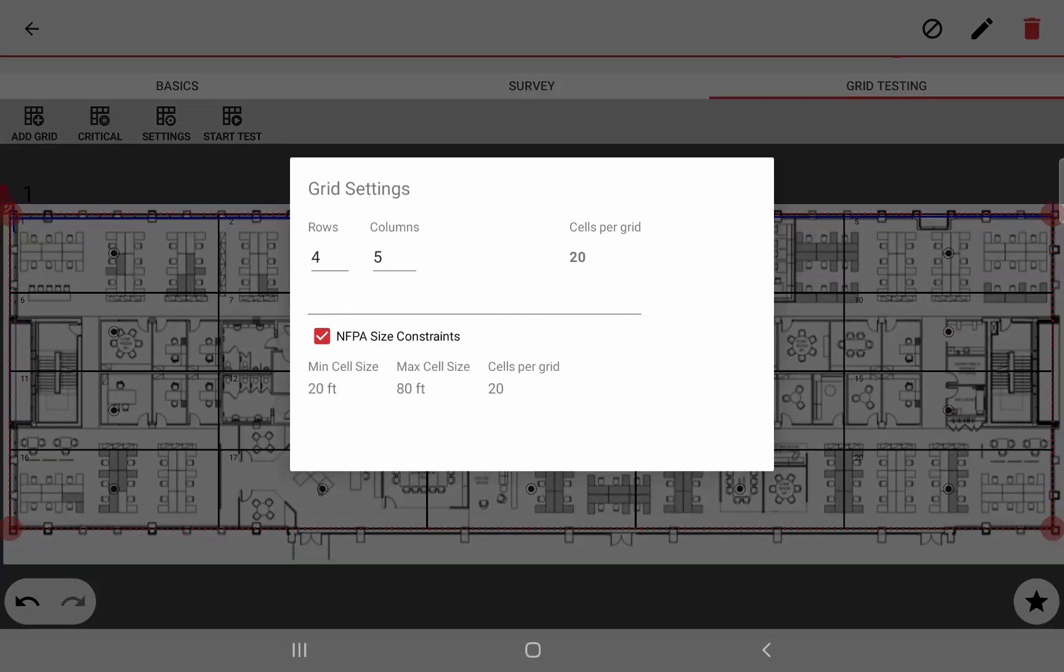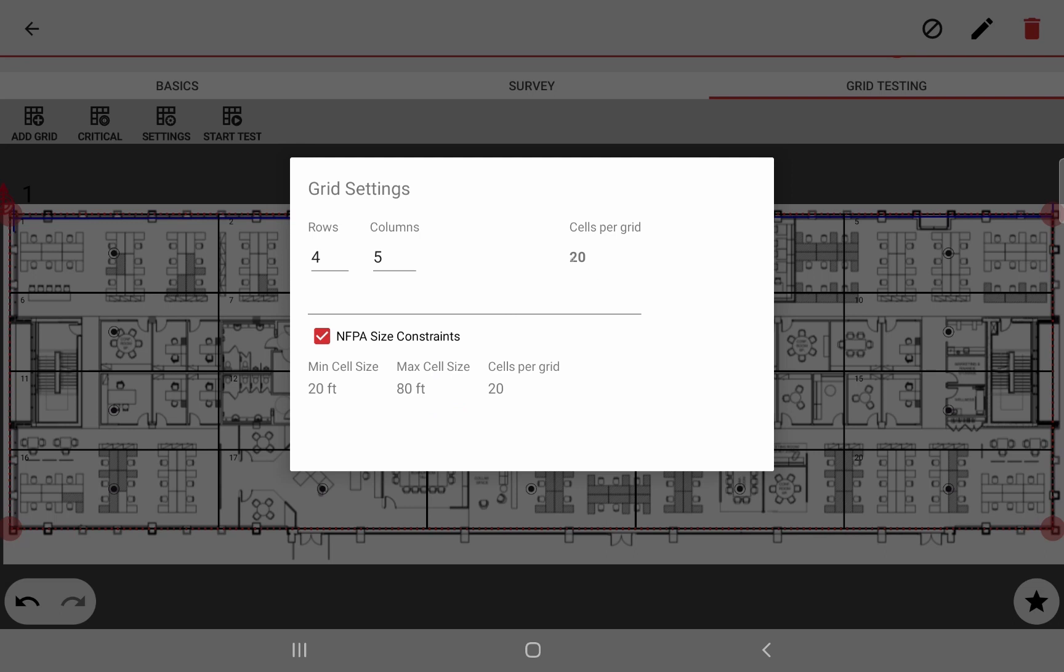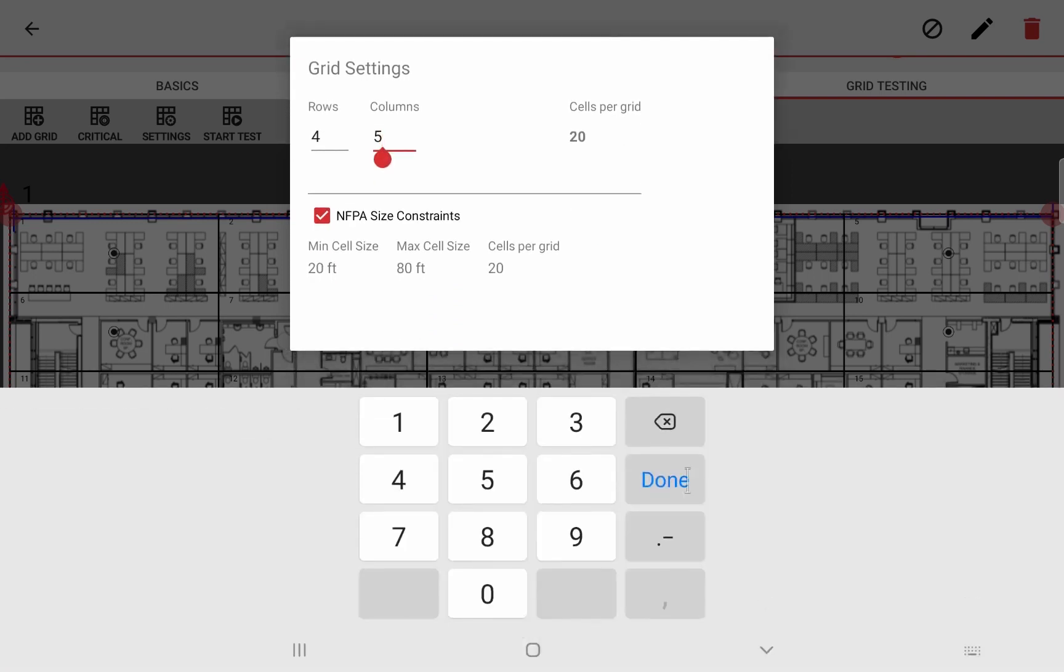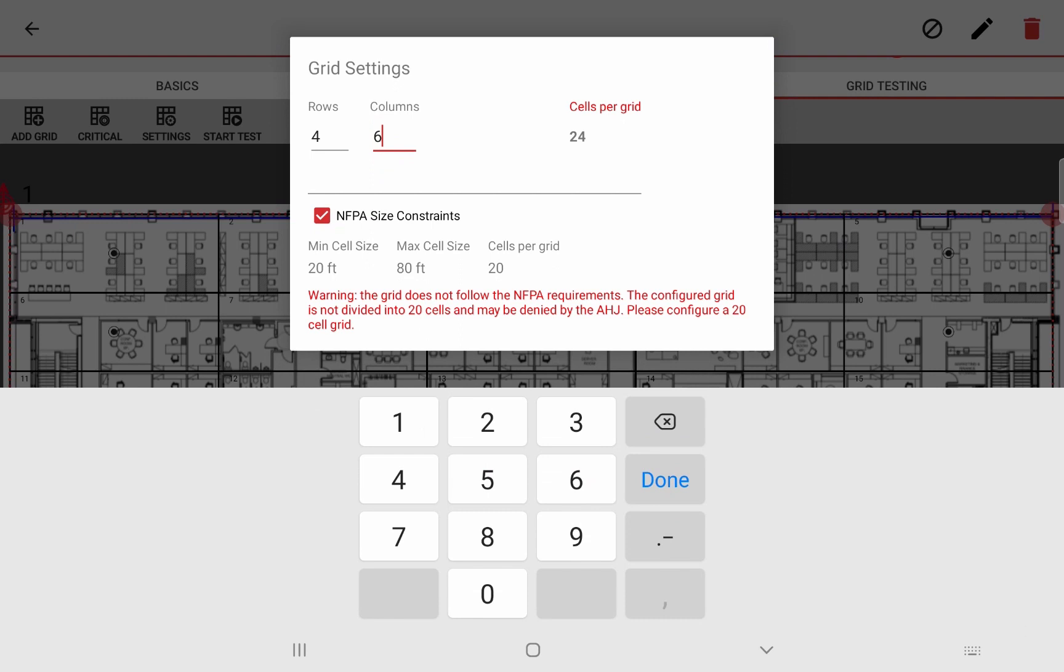Pop up in the grid settings. In the bottom, you can see we have a checkbox and NFPA size constraint by default, this will limit the size of the grid to have a minimum of 20 foot per cell size and a maximum of 80. So if you go above or under, it won't let you draw it and you want 20 cells per grid as the NFPA documentation recommends.